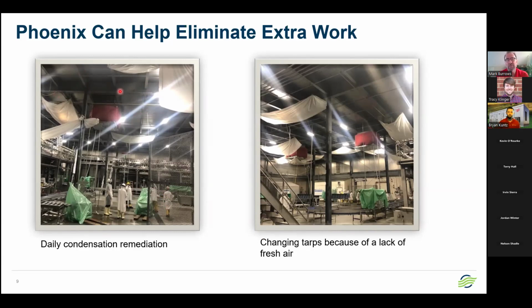It was more of a warehouse. So basically, they moved all their production stuff in here and tried to keep this at 45 degrees. And every single night, when they go into sanitation, that hot water hits the floor, that vapor rises up. It's all about dew points, right? It's going to condense wherever it can on that ceiling. And there are lots of opportunities for bad things to happen on that ceiling.